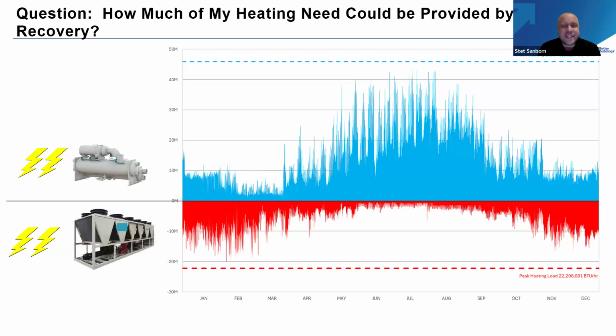What I see too often is folks just rip out the boiler and throw in a heat pump. And the very scientific number of electrical arrows or electrical diagrams on the left is just showing that you're likely going to double your connected electrical load if you just throw out your boiler and add a separate set of heat pumps just to cover your heating load. And there's a much smarter way to approach a load profile like this. And we can see that on the next slide.